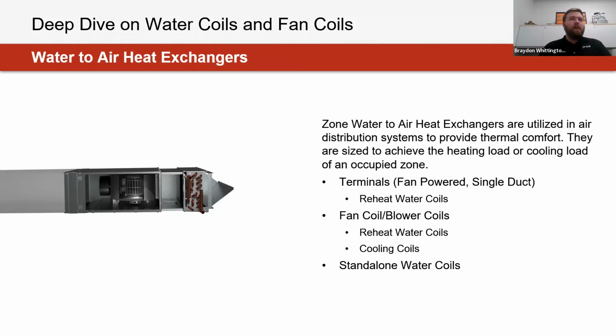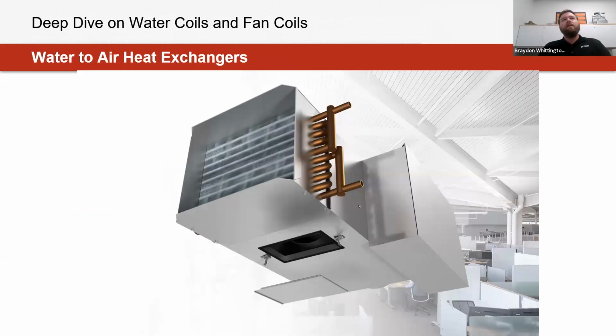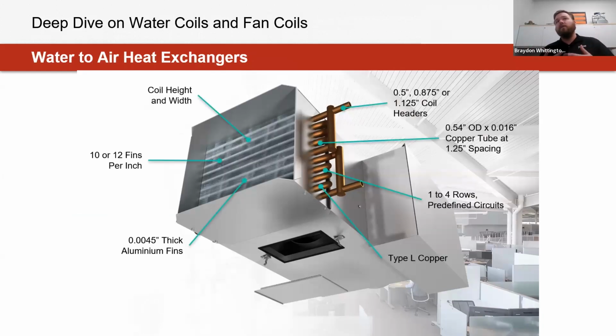But when we actually focus and take a look at the coil itself, what we realize is there's a lot of different components and features that actually go into putting this coil together, whether it be its overall size, how many fins or what type of material is going to be used, the type of spacings, manifolds, headers, and then even the amount of rows or circuitry that's put into the coil itself there too. And what we'll learn here in a little bit is that each of these little things that are called out do have a play, whether it be on the design side of what's capable from a manufacturer level, or also from a performance level of having an influence on what you're going to be seeing on your schedule or when you're connecting to this equipment within the field.